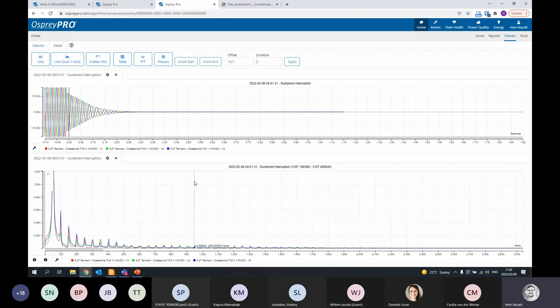You can do it on Osprey PRO. So if you set a trigger up correctly on Osprey PRO to trigger a waveform recording, you can then use that recording and do an FFT on that to view your switching frequency, for example. You can also do a scheduled recording or a triggered snapshot. So if you don't want to wait for some event to trigger, let's say you want to trigger when there's a transient, and you want to then view the waveform of the transient and do an FFT, you can do that.